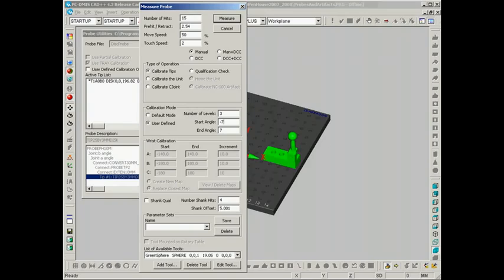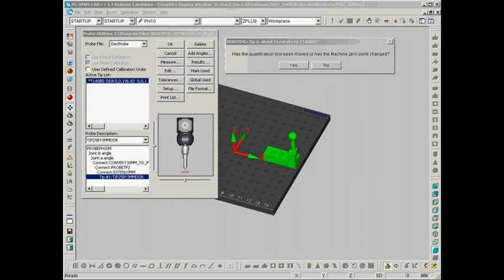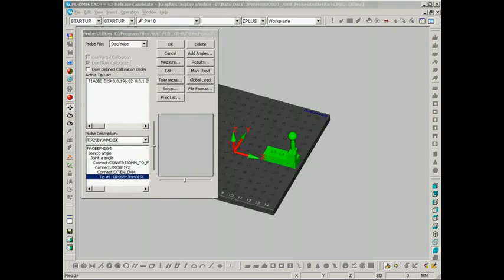The next thing you want to do is make sure that this is on DCC and not DCC plus DCC or any of the other ones. We want it to go straight to the sphere and do those 15 hits. So if we hit measure now, it's going to go ahead and calibrate our disc probe. Now, when you're presented with a dialog that says, has the qualification tool been moved or the CMM 0 point changed, you are now going to select no, because we have previously located this calibration artifact.